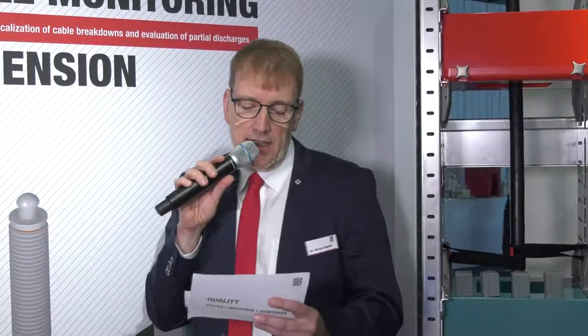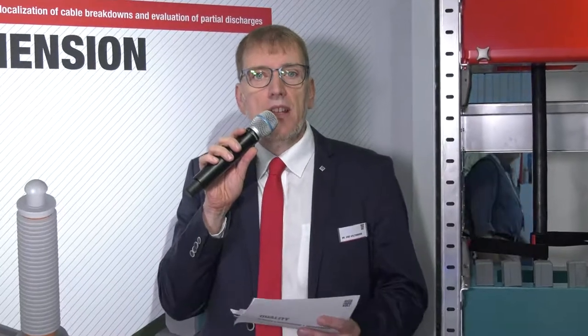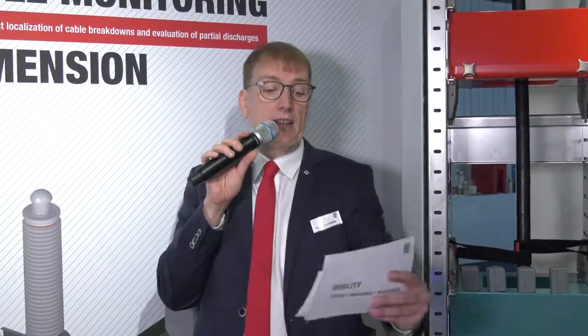Yeah, cable joints, this is another important topic here. We need to anticipate also that the probability of failures are most likely caused also by the cable accessories here, the terminations and the cable joints. And when we are looking in some of the CIGRE brochures taking care of reliability surveys, then we can find out that accessories, especially the joints, are one of the key elements which tend to fail more often in the cable system. To refer correctly to that, the technical brochures 815 and 379, these are the two brochures which have a complete overview about the reliability and failure mechanisms in high voltage AC and DC cables.